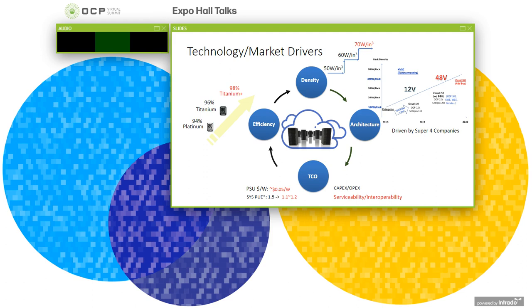To the right, here shows one trend: as rack density increases, traditional embedded redundant power supply will have to move out of the server chassis and use a shelf solution. I define this as Cloud 1.0. Now as density keeps increasing, a 12-volt shelf will not be able to handle thousands of amps of current, so a 48-volt bus came into play, which I call Cloud 2.0. If the rack density trend keeps going up, we can expect Cloud 3.0, which may have to use liquid cooling and other new technologies to keep up with the density demand.